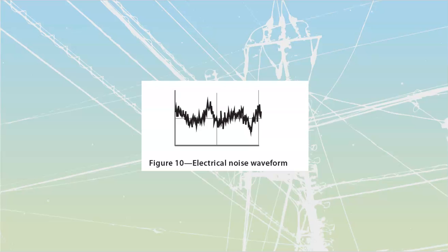Arcing gives us this. If you see consistent noise on the line, it's usually because we have consistent arcing happening. We know about AFCIs on residential systems that are designed to monitor and look for this type of waveform and kick out. Industrial systems can also have arc fault detection, done through CTs placed around the line, looking for amplification of these types of signals so they can kick those things out.